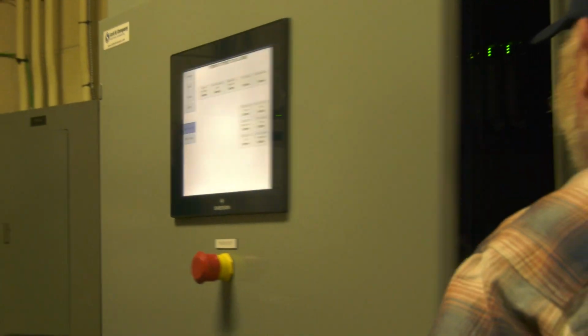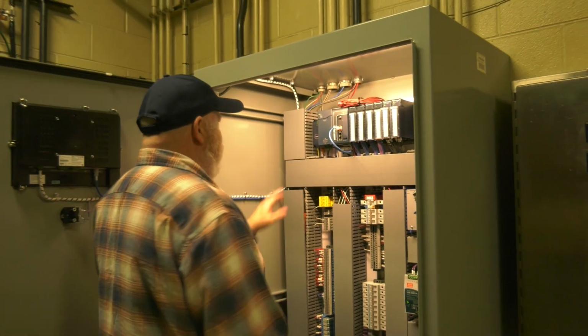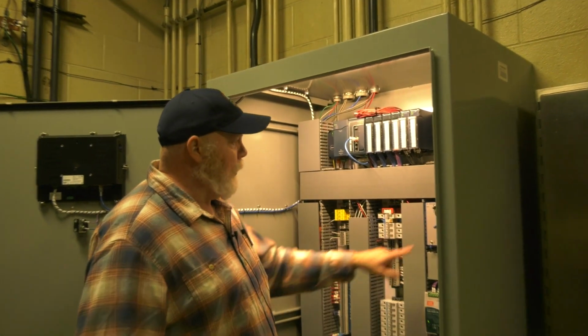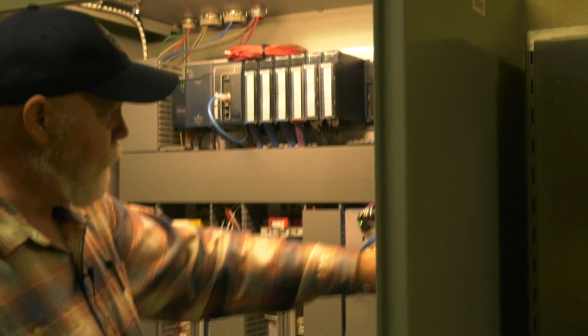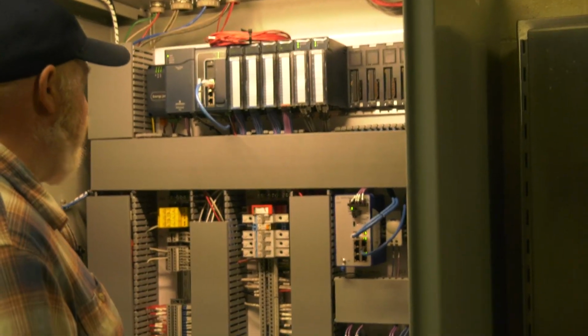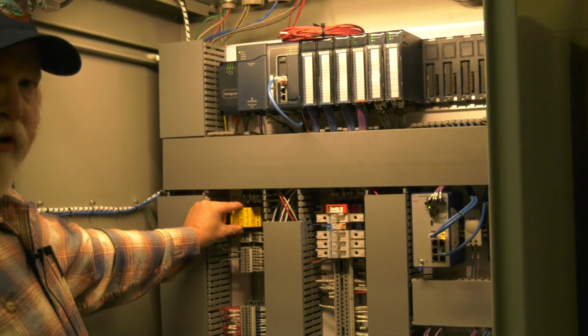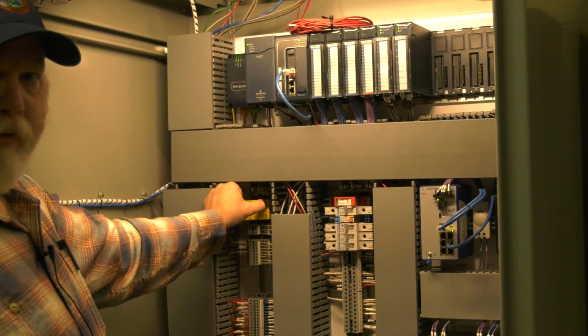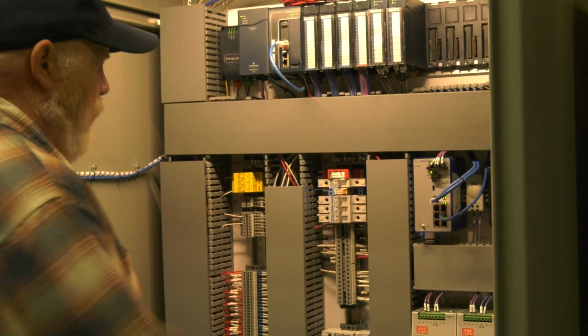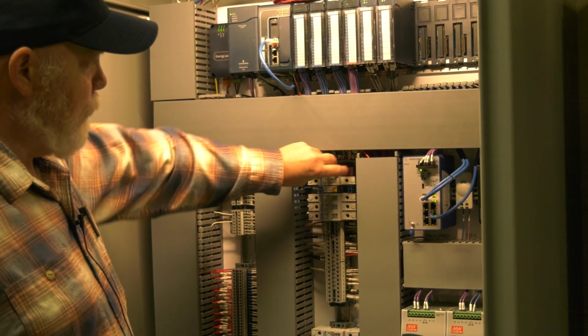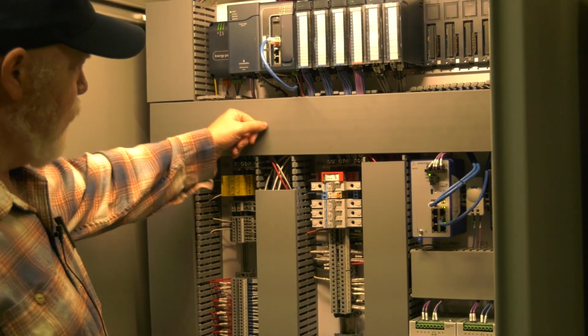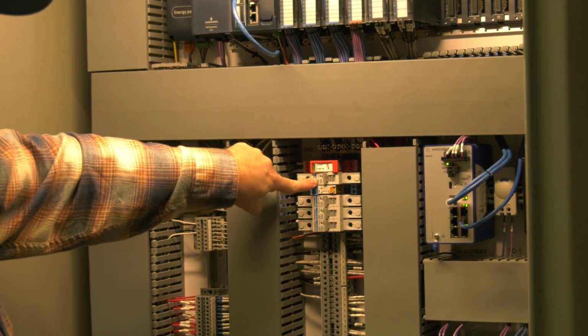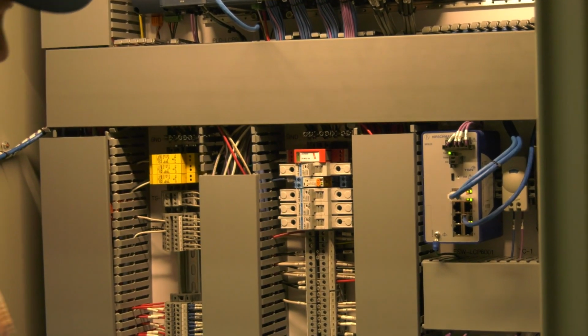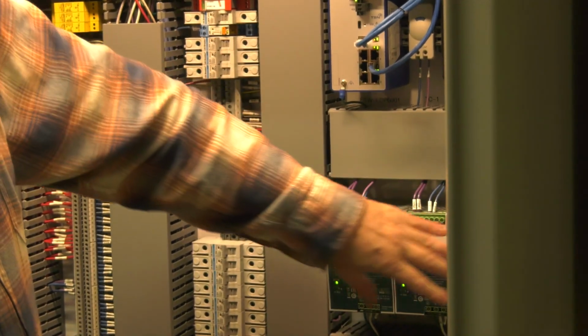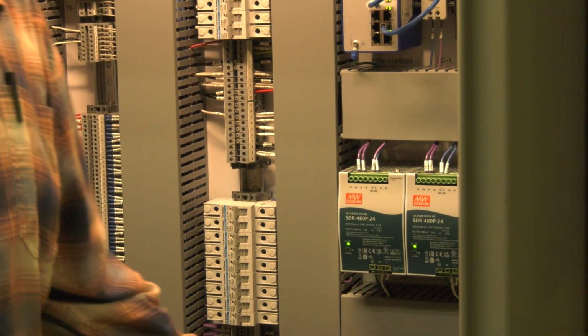All right, in here we've got our PLC, Ethernet switch, GFI receptacle, analog surge suppressors. These modules can be replaced. 120 volt surge suppressor, again the module pops out and can be replaced easily. This is your main circuit breaker. We've got 2 redundant power supplies, that's redundancy modules.